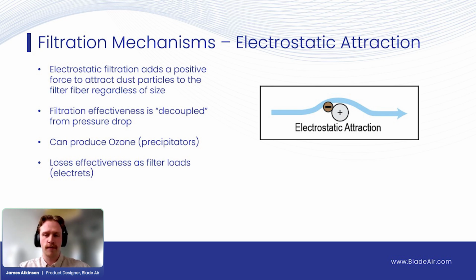There are a few different kinds of electrostatic filtration. Some, called precipitators, are used more for process air. They have a grill on the inlet side that charges the air and the particles, and then a positively charged plate on the outlet that traps those charged particles.